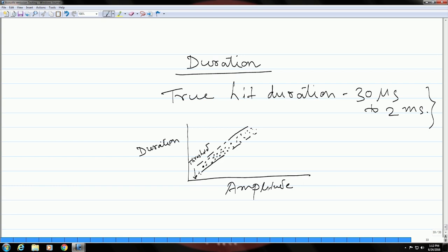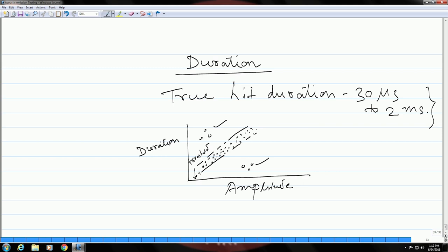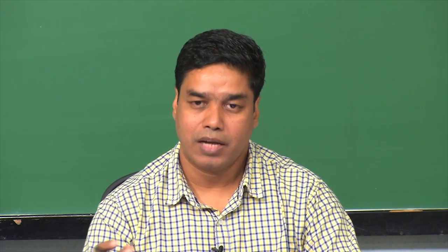You might also observe some discrete signals coming outside this band — for example, something above the band or below the band. Since these are not falling within the particular band, this is indicative that although they are being picked up by the sensor, they are not coming from actual acoustic emission events related to defects and damage in a component. You should have some idea about what non-relevant sources of emissions might look like.